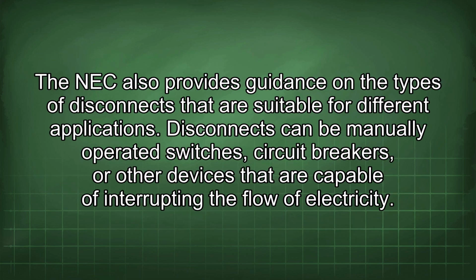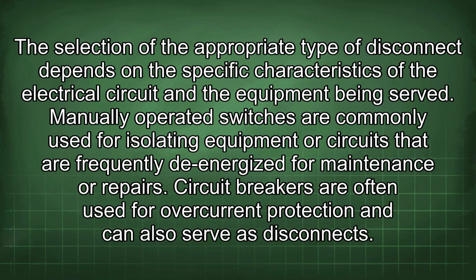The NEC also provides guidance on the types of disconnects that are suitable for different applications. Disconnects can be manually operated switches, circuit breakers, or other devices that are capable of interrupting the flow of electricity. The selection of the appropriate type of disconnect depends on the specific characteristics of the electrical circuit and the equipment being served. Manually operated switches are commonly used for isolating equipment or circuits that are frequently de-energized for maintenance or repairs. Circuit breakers are often used for overcurrent protection and can also serve as disconnects.